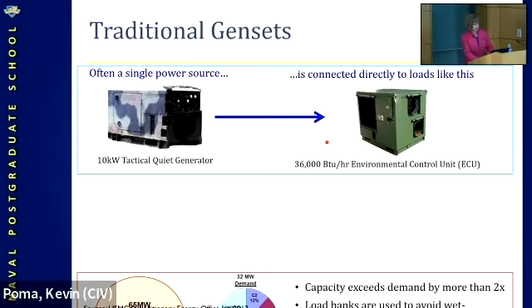But there is another thing about these generators. First of all, they produce CO2, they're diesel, they burn fuel. Second, they're typically oversized. For example, from a US Marine Corps brief, a genset of 65 megawatts served a load of 32 megawatts - it's half the size.